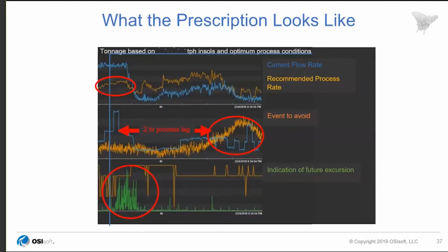So this is one actual use case from a mineral mill, and I'm going to be showing you some things here on the screen. They recognized, after doing some pattern recognition, that this line at the bottom, whenever there was a high vibration, hours later, it would lead to a problem in the process. So the whole process will get out of sync. It will start creating issues. In some cases, it could shut down the plant or the mill, and that's exactly what they were trying to avoid. So they knew that they could somewhat control the vibrations, but still these events were going to happen.